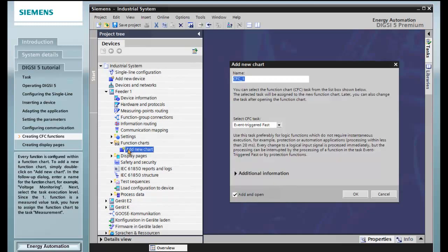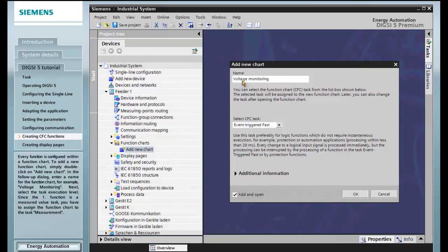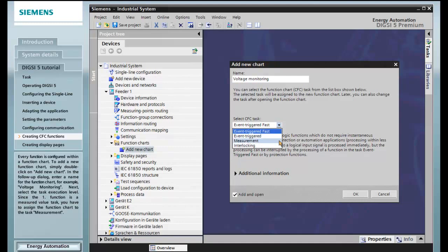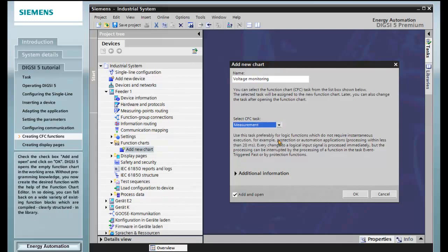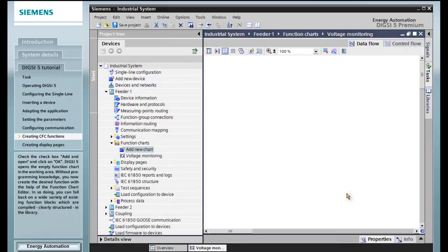Every function is configured within a function chart. To add a new function chart, simply double-click on Add New Chart. In the follow-up dialog, enter a name for the function chart, for example, Voltage Monitoring. Next, select the task execution level. Since the first function is a measured value task, you have to assign the function chart to the task measurement. Check the checkbox Add and Open, and click OK. DIGSI 5 opens the empty function chart in the working area.